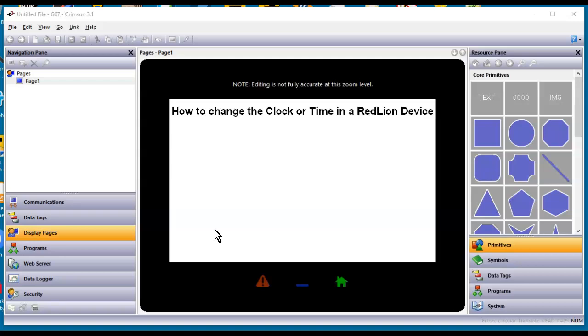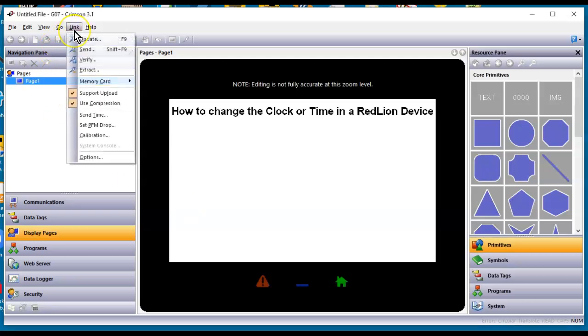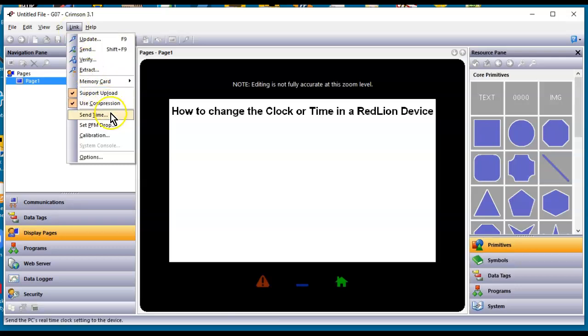The first method, and probably the easiest method, is if you're connected to your RedLion device over USB or Ethernet to download, you can always go to the Link pull-down menu, and you can click on Send Time. That will send the time from your PC down to the RedLion device real quick and should synchronize the clocks between the two, and you should be off to the races. That's the first and simplest way.